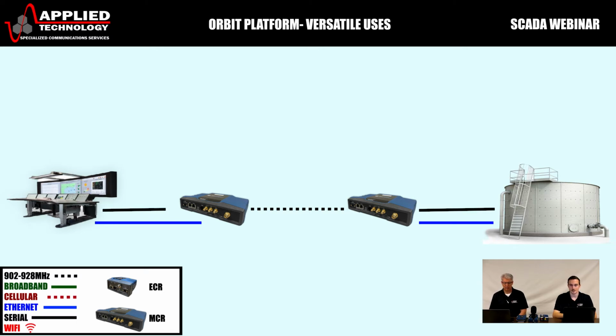That is an excellent point. You do want to make sure, typically when you are swapping over to Ethernet, there is a little more data required for each packet of Ethernet versus serial. Everyone knows Ethernet is going to take up more bandwidth. So you want to make sure your signal connection is up to par every time. Every time you're doing a new deployment, you want to test it out beforehand. Make sure you do the proper surveys, which, as Jeff mentioned earlier, we do assist with as well. So if that's needed, feel free to contact us.